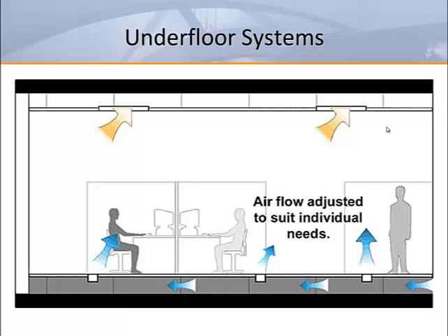The thermostat control from the office is no longer necessary as the office occupant has manual adjustability of the floor diffusers. Many studies have shown that the more control occupants have over their own thermal comfort, the more comfortable they will be and the more productive they will be. A major advantage of underfloor air distribution is the accessibility to service cables when a space is reconfigured. This is also known as churn. For a school application, this may be a computer lab.